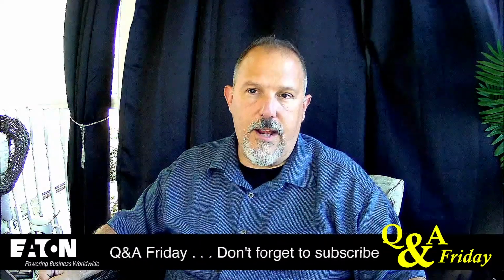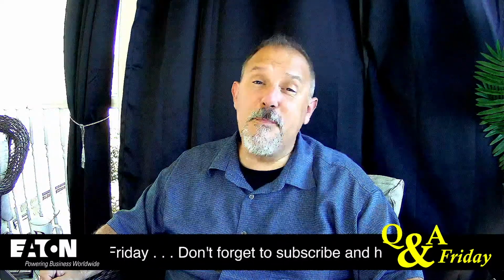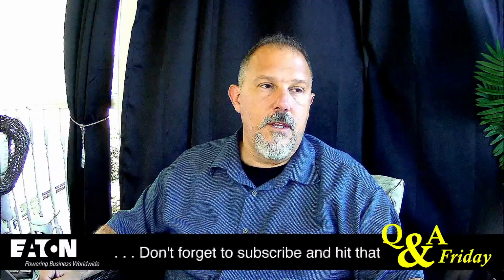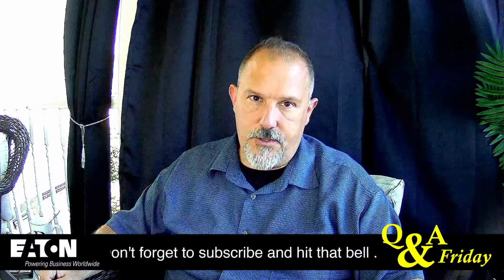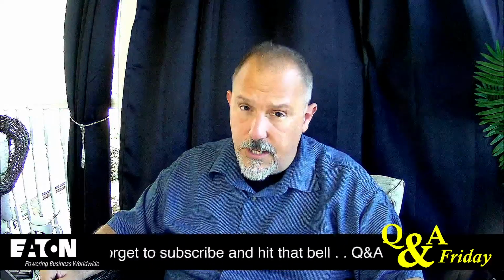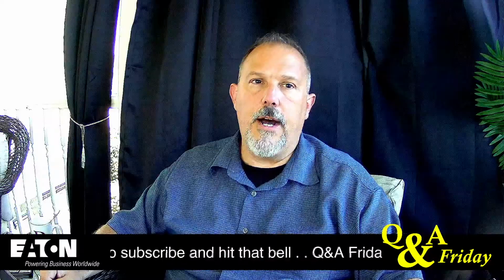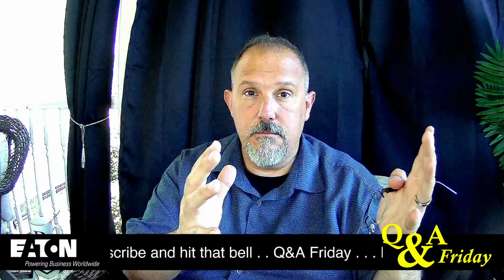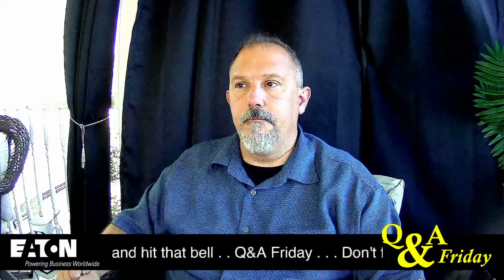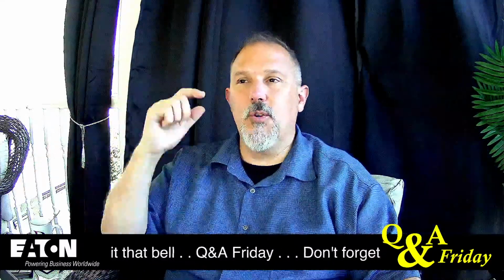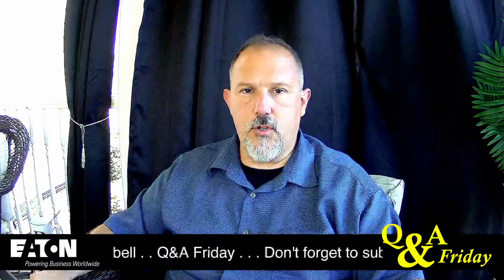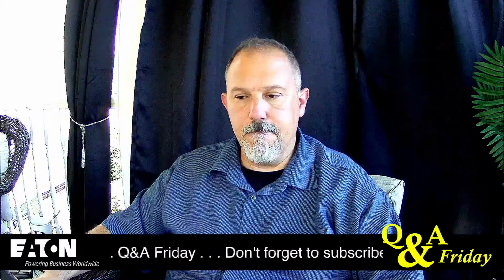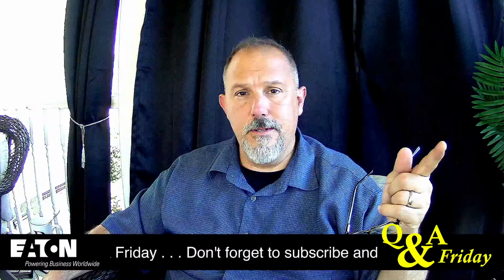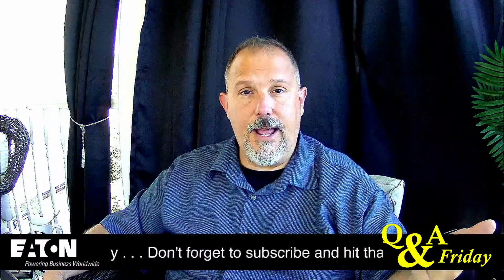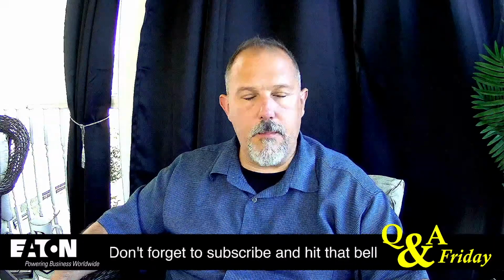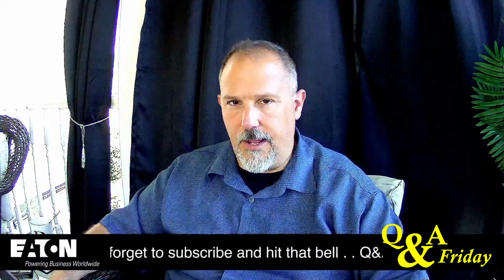The challenge is, whenever you get into arc flash, especially arc flash, you look for standards. Now, we have arc resistance standards. We have standards that help you identify compartmentalization. We have standards we can fall back on. So what you would want to do is look at the motor control center, converse with the manufacturer, and say, how is that listed? If there's a barrier, you're going to want to know, is it listed to the standard that permits the compartmentalization? I can't remember the number off the top of my head.